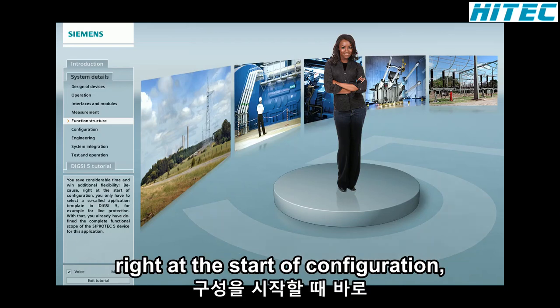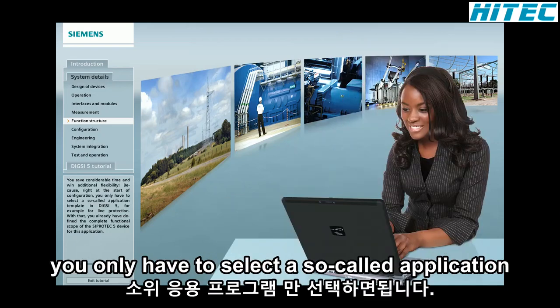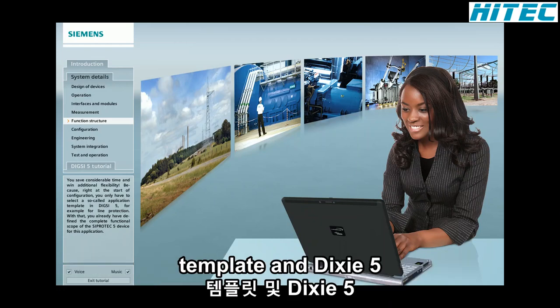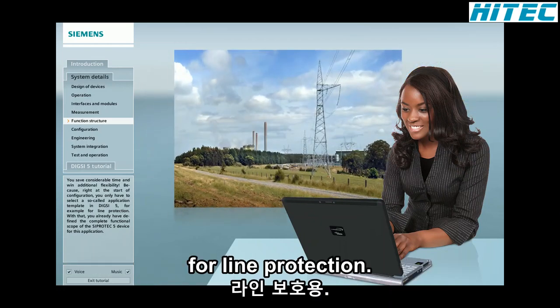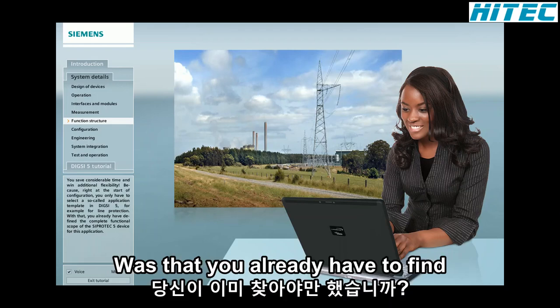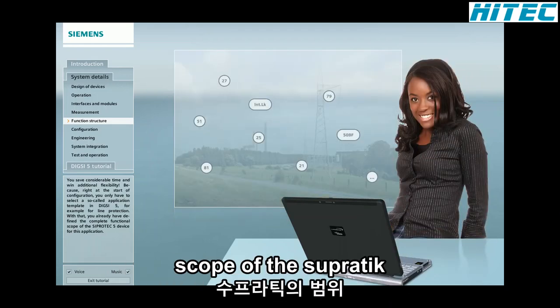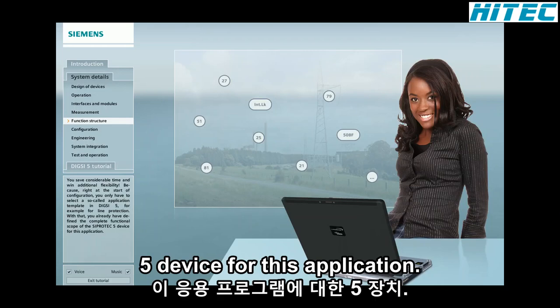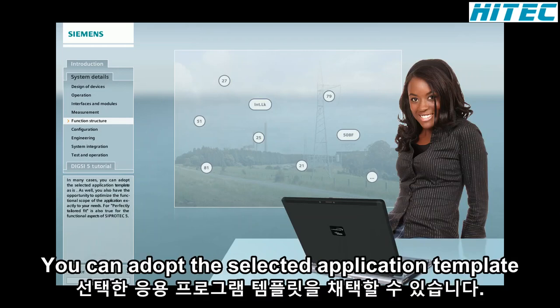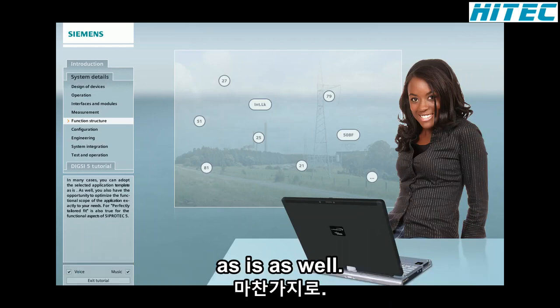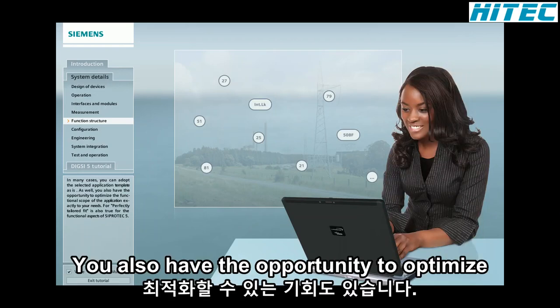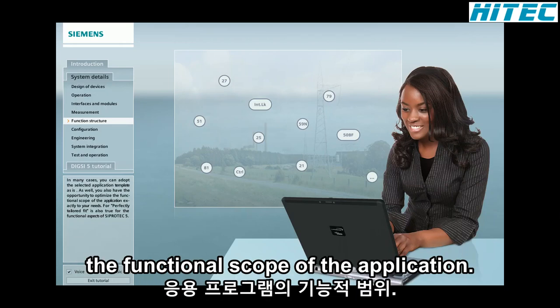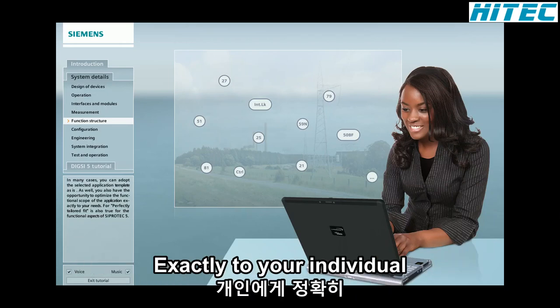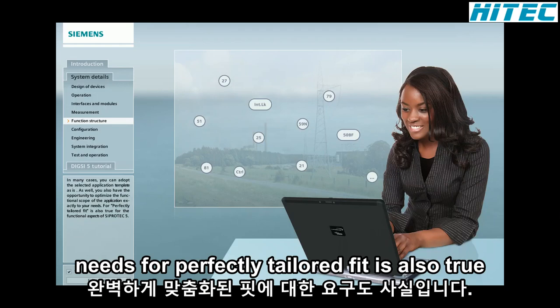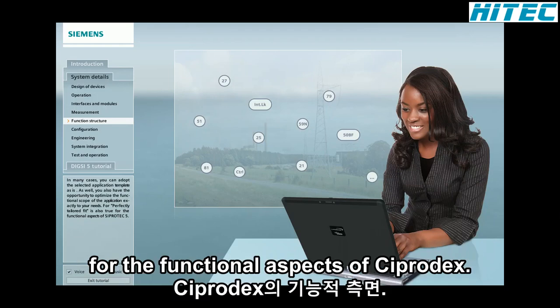Because right at the start of configuration, you only have to select a so-called application template in DIGSI 5, for example, for line protection. With that, you already have defined the complete functional scope of the SIPROTEC 5 device for this application. In many cases, you can adopt the selected application template as is. As well, you also have the opportunity to optimize the functional scope of the application exactly to your individual needs. For perfectly tailored fit, it is also true for the functional aspects of SIPROTEC 5.